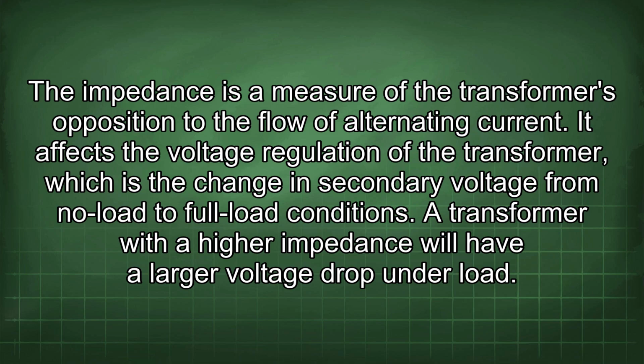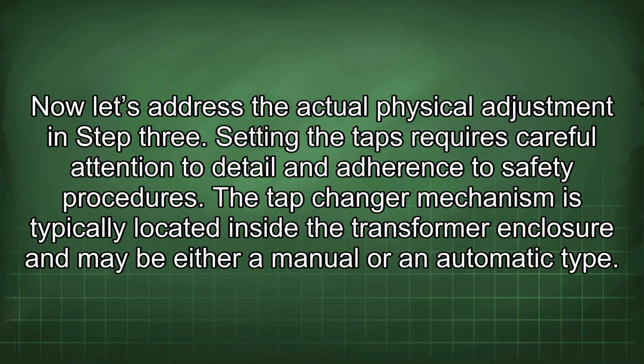A transformer with a higher impedance will have a larger voltage drop under load. Now let's address the actual physical adjustment in step 3. Setting the taps requires careful attention to detail and adherence to safety procedures. The tap changer mechanism is typically located inside the transformer enclosure and may be either a manual or an automatic type.